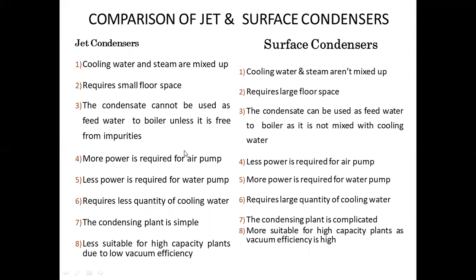More power is required for the air pump in a jet condenser as compared to a surface condenser, while less power is required for the water pump in a jet condenser as compared to a surface condenser. In a jet condenser, less quantity of cooling water is required as compared to a surface condenser.